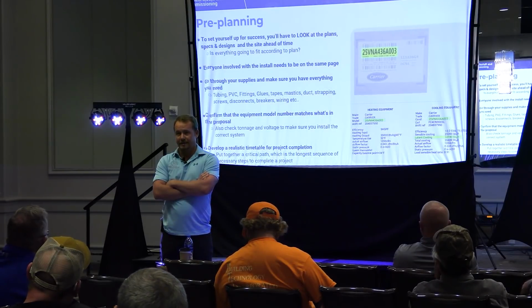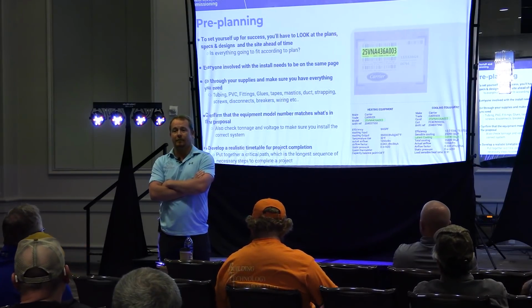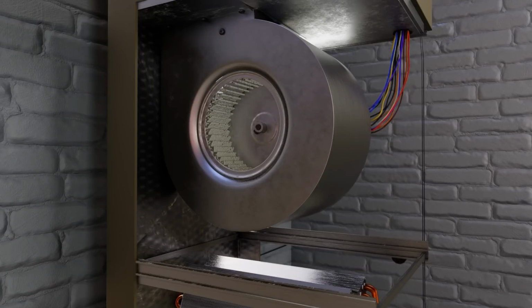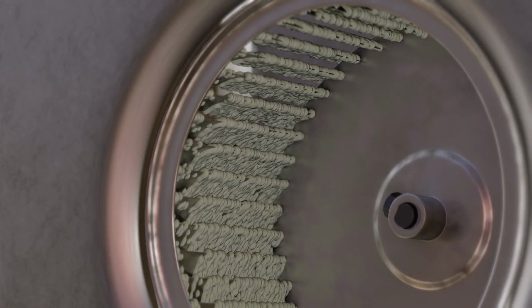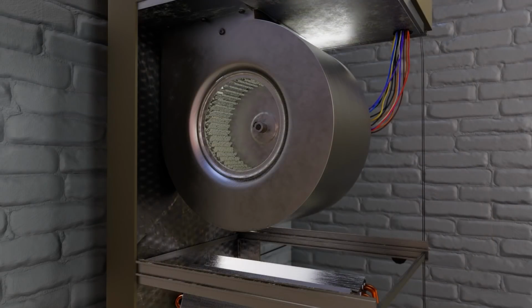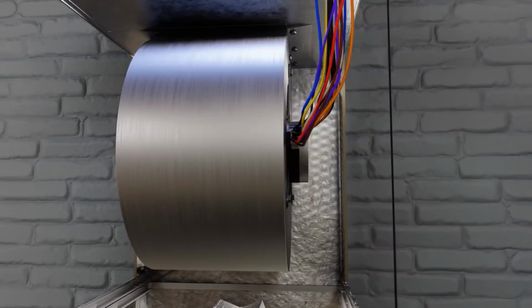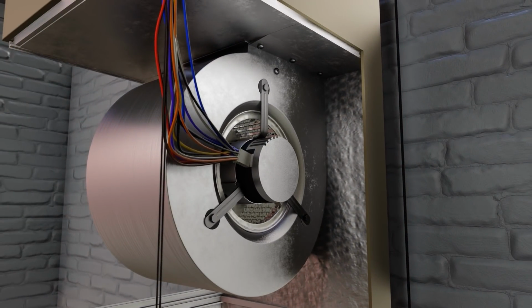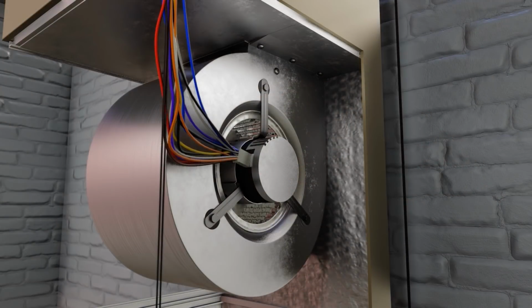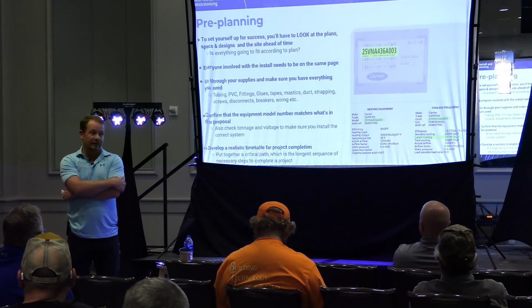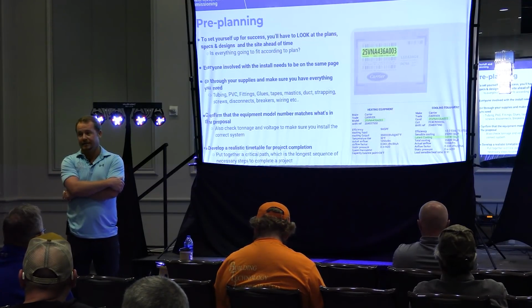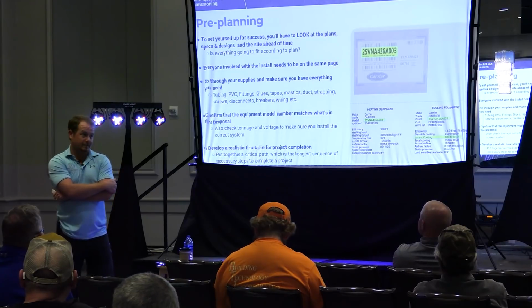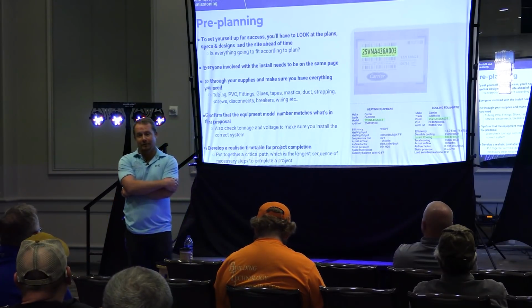The blower wheel gets down to temperature. If you think about the position of that blower wheel, have you ever wondered why they get so nasty dirty all the time? It's because they do condense — sometimes those suckers will flick water out at you. That's because the blower wheel is sitting just inches away from the evaporator coil. And radiant heat is a factor of distance, right? So that blower wheel becomes nearly the temperature of the evaporator coil in a lot of cases, and it will condense, especially if the coil isn't pulling moisture off like it should.